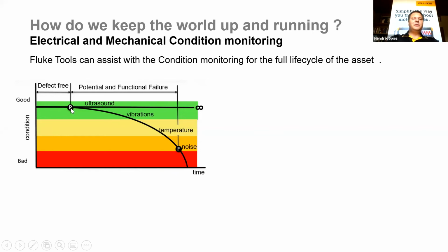So you install this new motor and pump combination. For the first year, 2 years, everything is good. But then you'll start to get aging on the bearings, on the electrical windings of the motor. So obviously you've got a potential of failure and then a functional failure. So functional failure meaning the actual asset cannot perform the task anymore. So as you can see, we go down a path of aging. And as we go down this path of aging on the asset components, we can typically use ultrasound, vibration, and temperature to actually determine what is the severity of this actual potential and functional failure.